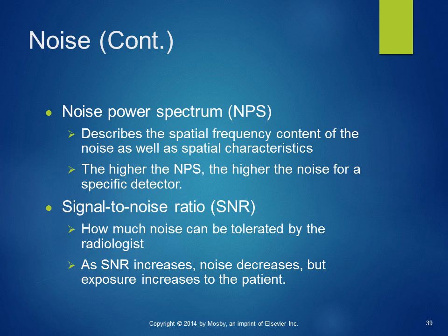Noise power spectrum, or NPS, describes the spatial frequency content of the noise as well as spatial characteristics. The higher the NPS, the higher the noise for a specific detector.